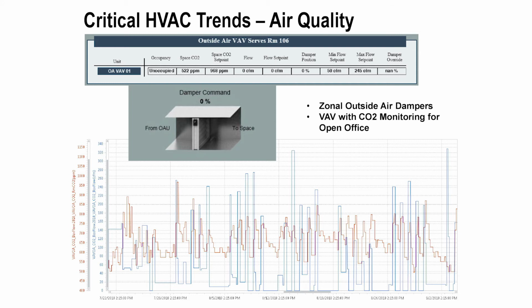weekdays are higher. But remember how we talked about the different groups that are in this facility? One of those groups, for some reason, put their schedule on 24/7. So that means that we have to provide outside air all the time. That means that the heat pumps are controlling to their occupied set points all the time. And that's the root cause of what happened here.